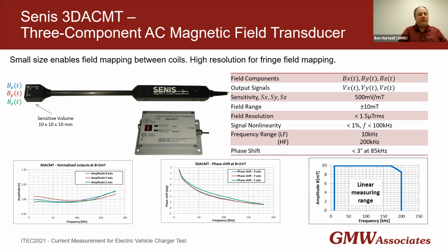The small physical size and small sensitive volume are useful for measuring the field between and around inductive charging coils. Now, while the field between the charging coils might be easy to model, it's still useful to be able to verify your model with a measurement. But what would be more tricky to model would be the environment, what other ferromagnetic materials you have around it. And so here, being able to have both the small physical size as well as the high field resolution, you can make a good map of the fringe field and how the field distorts and interacts with the environment around your charging coils.